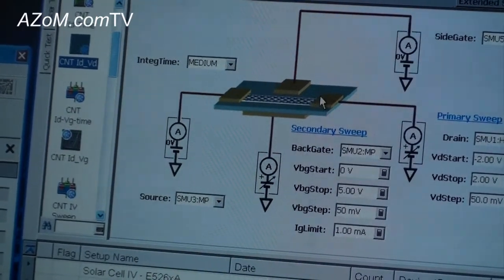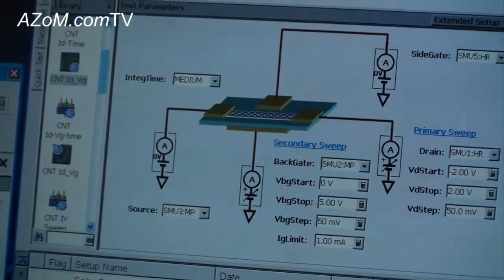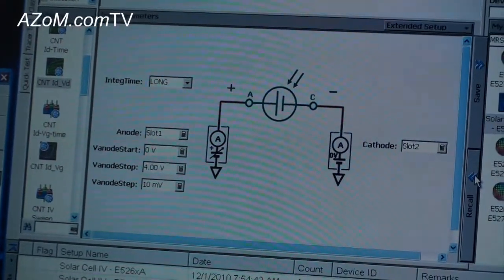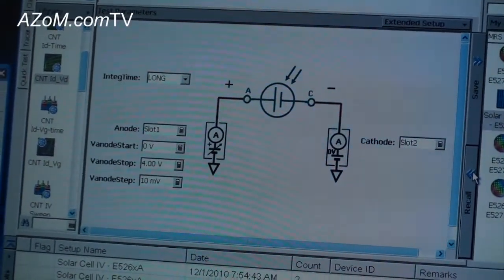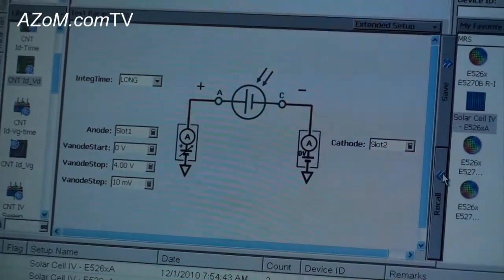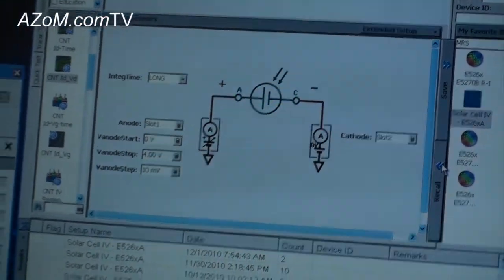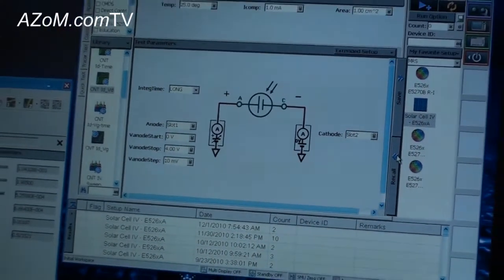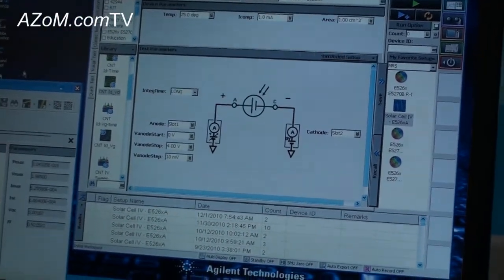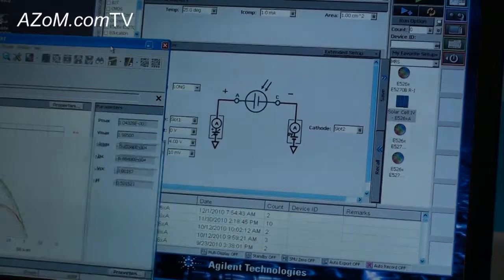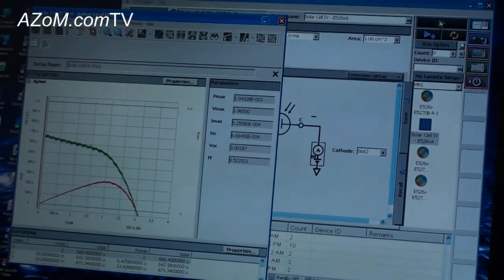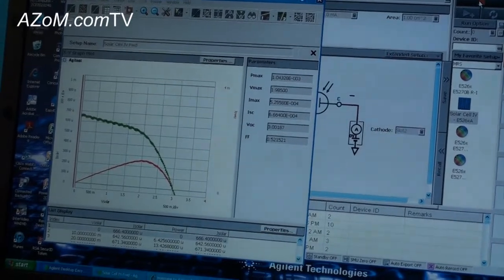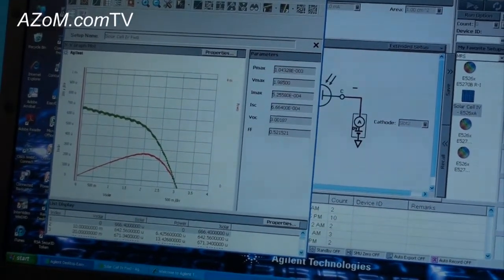In this case, what I've actually got the instrument set up to do is a solar cell test. I'm going to recall the instrument settings that I've saved — my favorite setup. You can see here I've got a nice little picture of a solar cell. Now I'm going to introduce a light source and make a measurement. This is a previous measurement, and when I click on the measurement button after a couple of seconds it will refresh and make a new measurement.